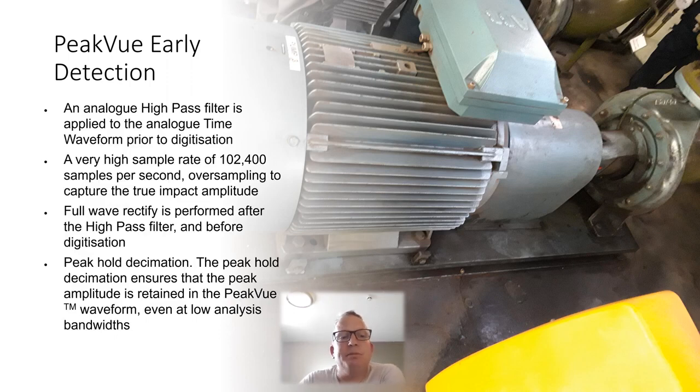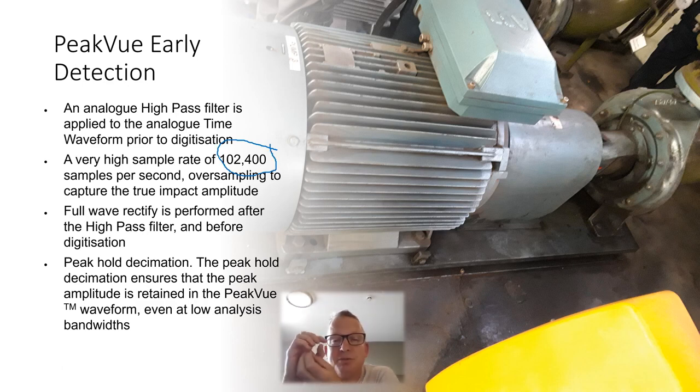Very basically we've got analog high-pass filter applied to the analog time waveform prior to digitization. The bit which sets them apart is this bit here, is where it actually has a sample rate of 102,400. So the analyzer is sampling so fast that it's going to capture these very, very short, transient, minute shock pulses from the bearing.